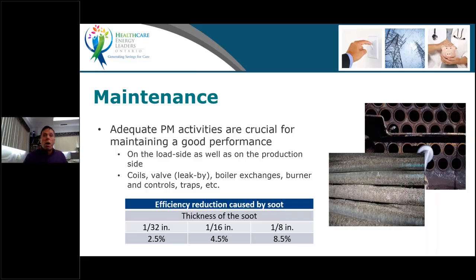On the boiler side, you also have the possibility of soot accumulation within the tubes, and you can also have a buildup of calcium or different thicknesses of buildup on the exterior of the tube on the water side if your water treatment is not adequate. That will also drastically impact your efficiency. Here in the table you have how efficiency will be reduced with different thicknesses of soot. We do have a similar table, which is not in the slide, for a buildup of calcium or other residue on the exterior side of your tube. So you've got to be really careful with your maintenance.